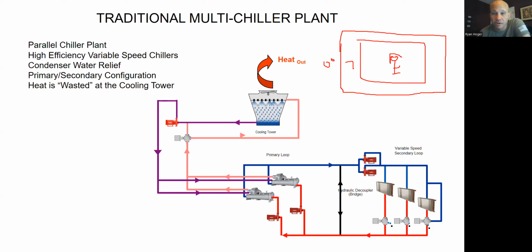On the building, if you are the interior zone, this is you. If it's 0 degrees outside or whatever temperature, okay, great. This zone right here is warmed up to 72. They got the heat going wherever they got, 72. This is 72. This is 72. All the perimeter zones got their heat on because it's 0 degrees outside and they have full glass windows. So they're all 72. So if this is me in the middle, I don't know it's 0 out. I think it's 72 all around me. All 4 sides of my zone, it's San Diego. It's 72. And the floor above me and the floor above me, everybody's 72.